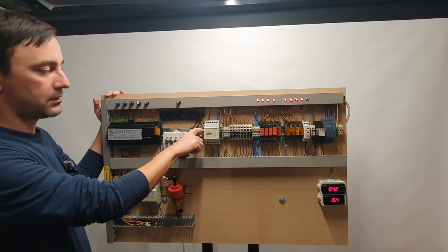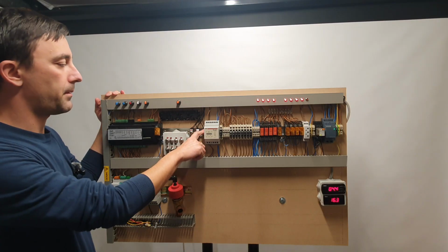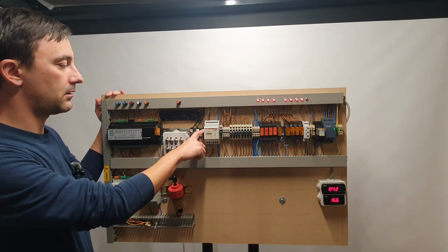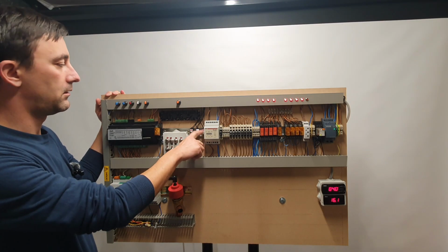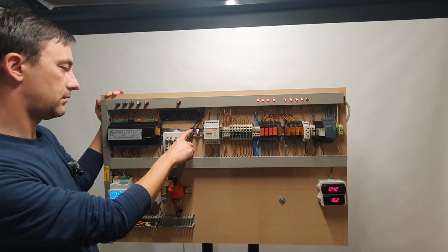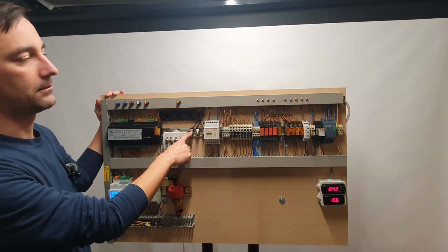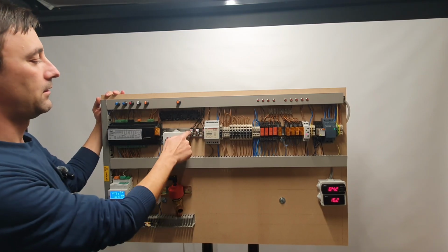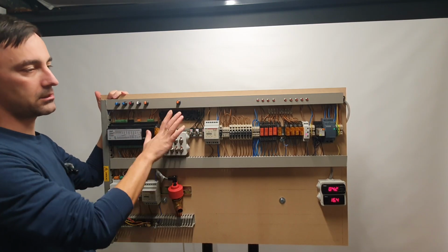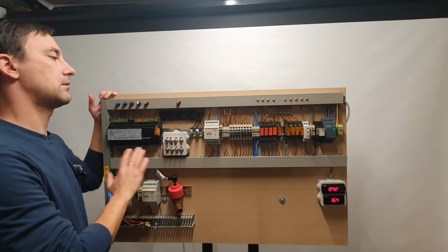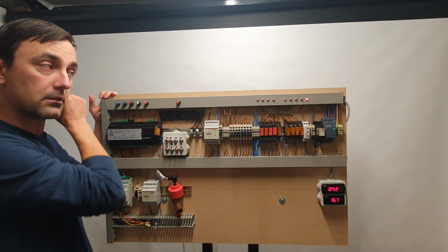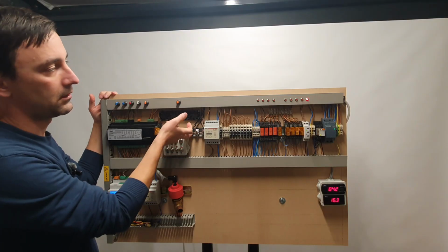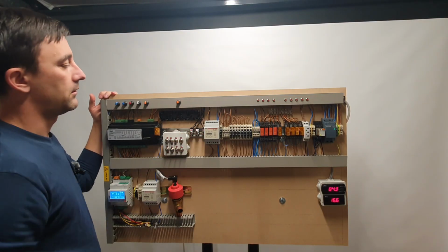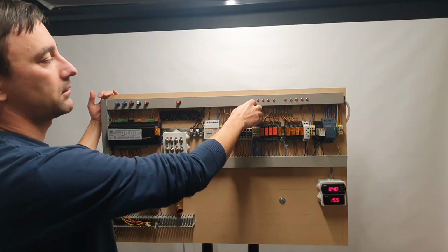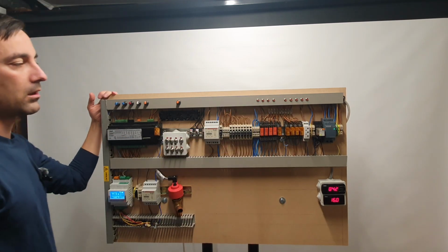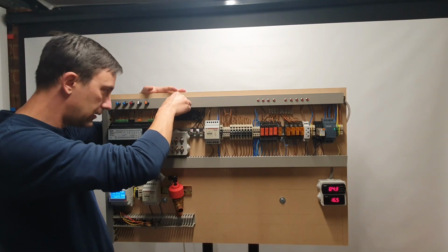So if I were to simulate a major fault with the pack, like a HP LP shutdown, which I think is this one, or this switch shuts down the pack, it senses that there's a major fault. I should say extremely high pressure. I turn it back, it will start bringing the compressors one by one. This one still does not want to work.